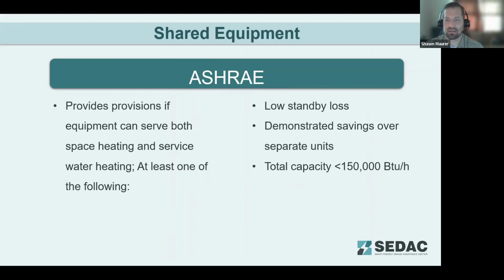Shared equipment. ASHRAE prefers to avoid sharing heating equipment between space heating and service water heating. There are some provisions here that do allow that under certain situations of low standby losses, demonstrated savings over having them as separate units, and limited capacity. The IECC does not include these kinds of provisions. They are usually separate systems.